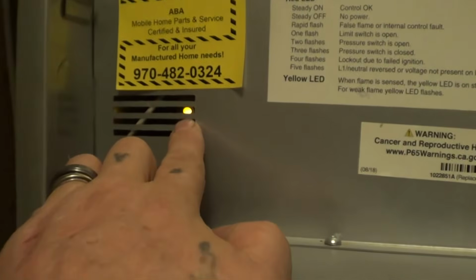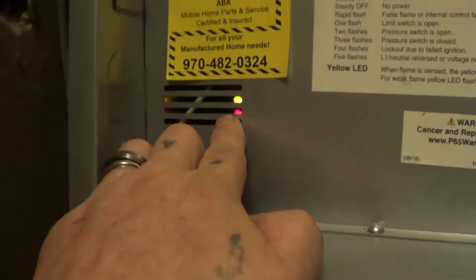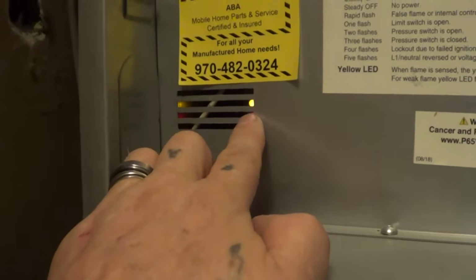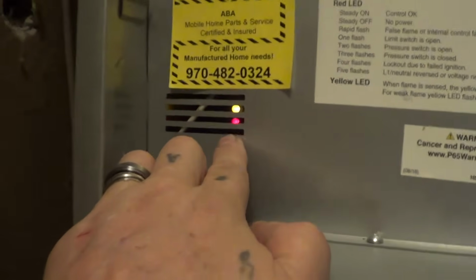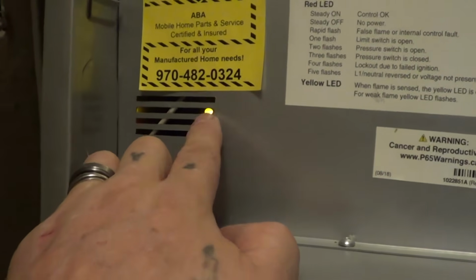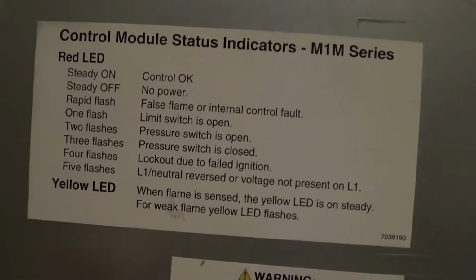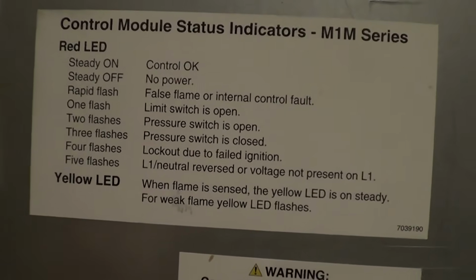We want to see a nice big flame. So we see a nice big flame there, blue towards the center, yellow towards the tips. That's a good flame. So now we can hear the main blower coming on. If you are having any problems with that, you probably won't have any yellow. If you have a flashing yellow, that just means that the flame is not a very great flame. We'll need to look at that. And if you have a flashing red light, so no yellow and a flashing red light, it'll tell you all the sequence right here, what's going on with this particular thing.